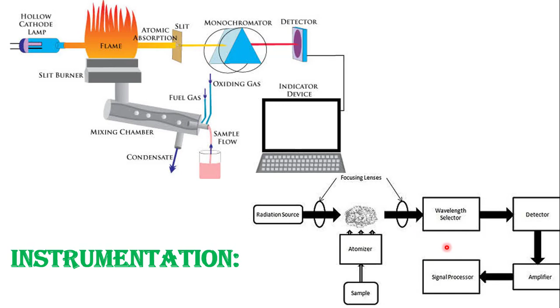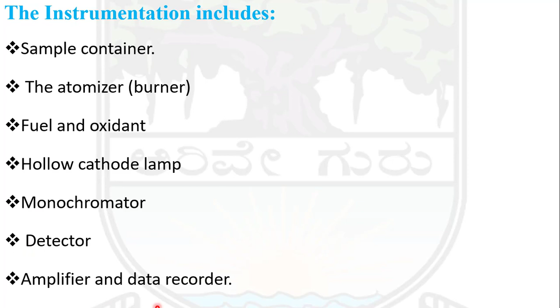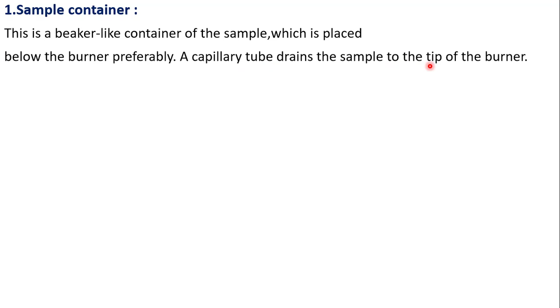The instrumentation includes sample container, the atomizer, fuel and oxidant, hollow cathode lamp, monochromator, detector, amplifier and data recorder. First one, sample container. This is a beaker-like container of the sample, which is placed below the burner preferably. A capillary tube drains the sample to the tip of the burner.